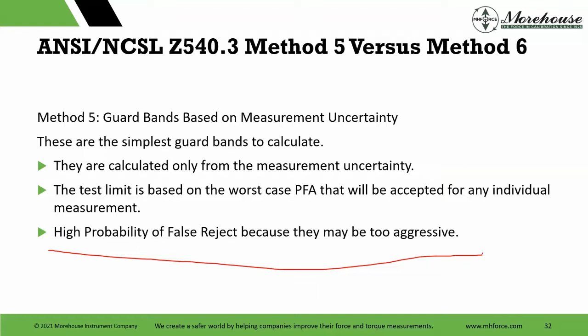So method 5, guard bands on measurement uncertainty. Simplest to calculate. We're just going to subtract the measurement uncertainty. Test limit would be based on worst case PFA. And the problem with these is you could have a high probability of false reject because they may be too aggressive. Again, that's on the Cal lab. If we reject something and adjust it, that's fine. That's on us.